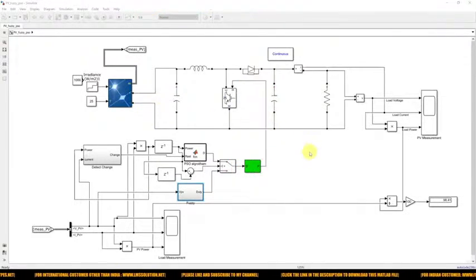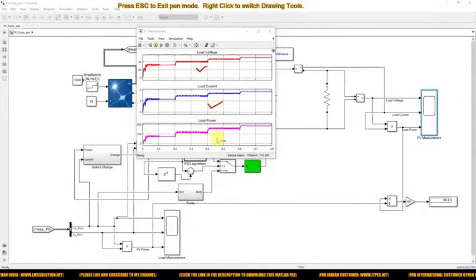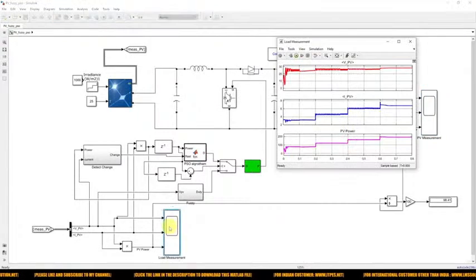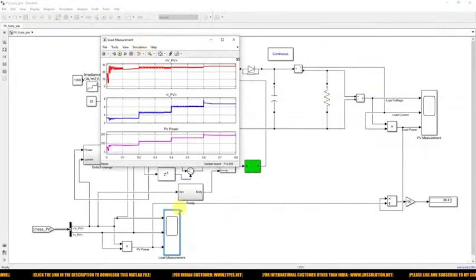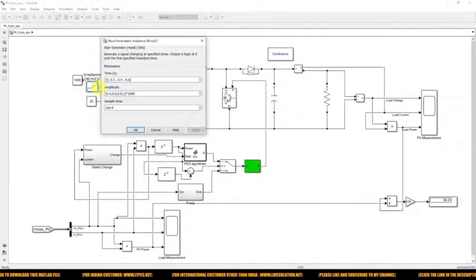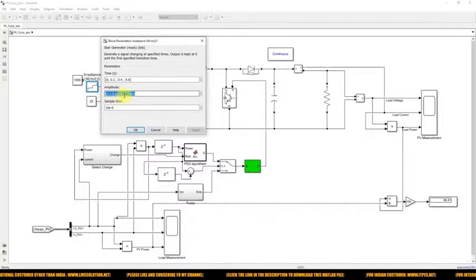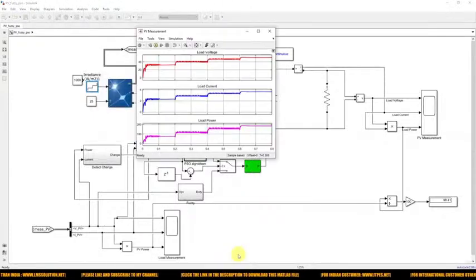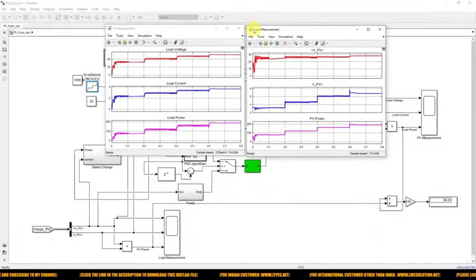The model is simulated with irradiation varying from 400, 600, 800, and 1000 W/m² every 0.2 seconds. The PV voltage is maintained around 26.2 to 26.6 V for all irradiation conditions — because at the maximum power point, the voltage of this panel is around 26.3 to 26.5 V for different irradiation levels. The MPPT adjusts the duty cycle to maintain the PV voltage at that range to extract maximum power.